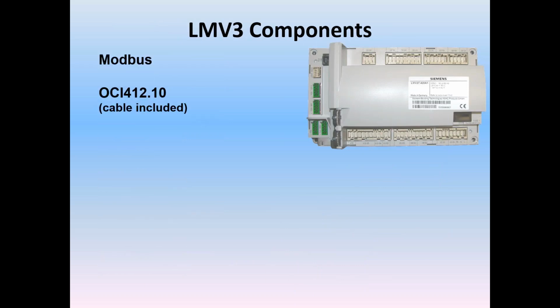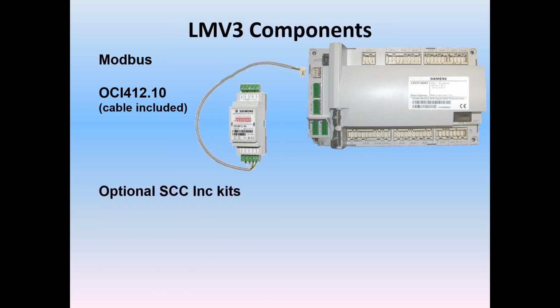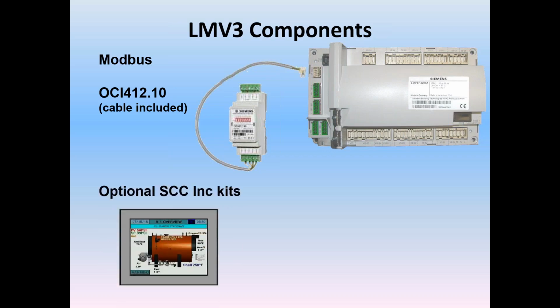If you want to add Modbus to your LMV3, you need to get an OCI 412. It includes a cable, and it plugs in, as you see on the unit right there, plugs into X92, and then coming out of that module, you'll get a Modbus connection that you can take to a BMS, to a touchscreen, to whatever you need to run Modbus, such as an optional SCC Inc touchscreen kit. That would be a Modbus device, and it takes all that data and presents it onto your screen.